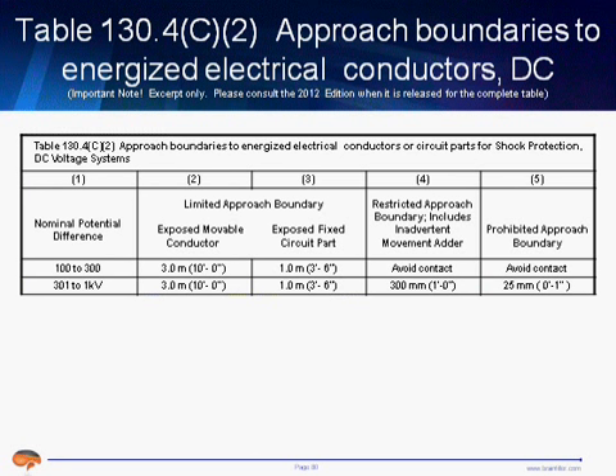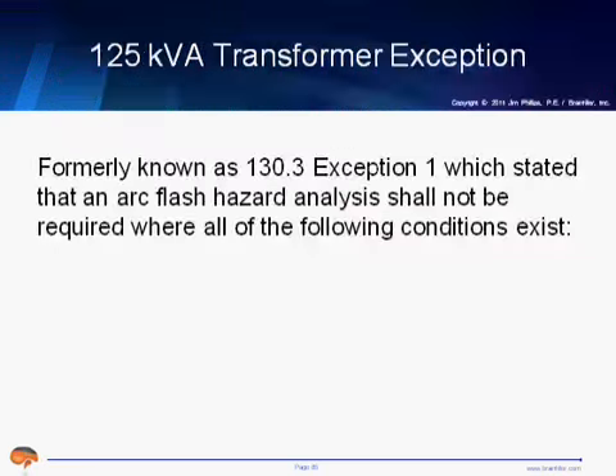The DC table lists by voltage, and then we have limited approach boundaries for the exposed movable conductor and exposed fixed circuit part. That's similar to its AC counterpart. We have the restricted approach boundaries, and we have the prohibited approach boundaries. So like we do with the AC table, you look up your DC equipment based on voltage, and you can locate the limited, restricted, and prohibited approach boundaries accordingly.